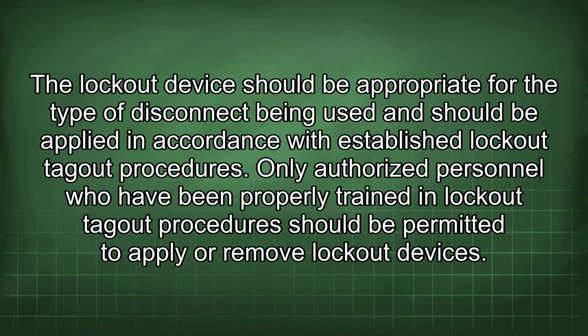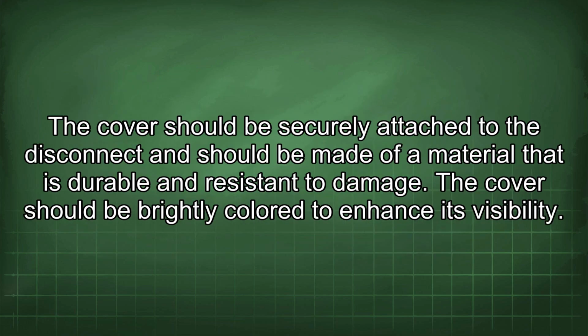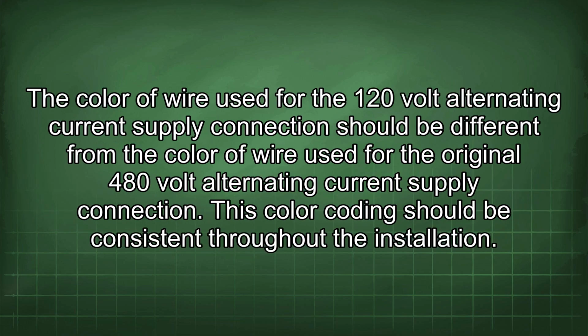The lockout device should be appropriate for the type of disconnect being used and should be applied in accordance with established lockout-tagout procedures. Only authorized personnel who have been properly trained in lockout-tagout procedures should be permitted to apply or remove lockout devices. The cover should be securely attached to the disconnect and should be made of a material that is durable and resistant to damage. The cover should be brightly colored to enhance its visibility. The color of wire used for the 120-volt alternating current supply connection should be different from the color of wire used for the original 480-volt alternating current supply connection. This color coding should be consistent throughout the installation.